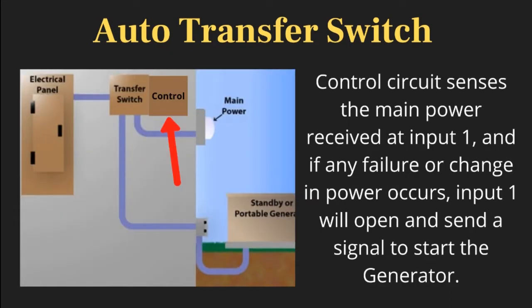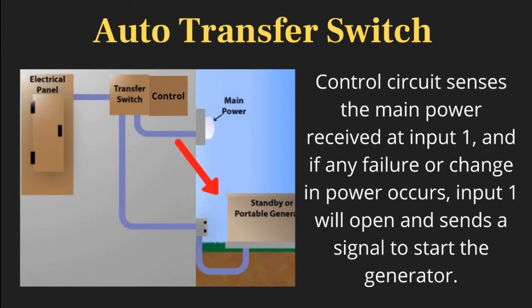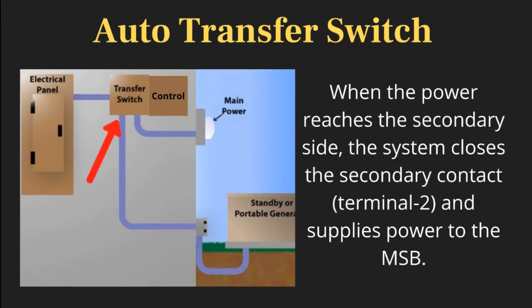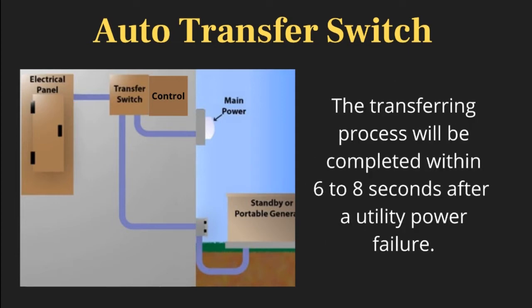The control circuit senses the main power received at input 1. If any failure or change in power occurs, input 1 will open and send a signal to start the generator. When the power reaches the secondary side, the system closes the secondary contact and supplies power to the MSB. The transferring process will be completed within 6 to 8 seconds after a utility power failure.